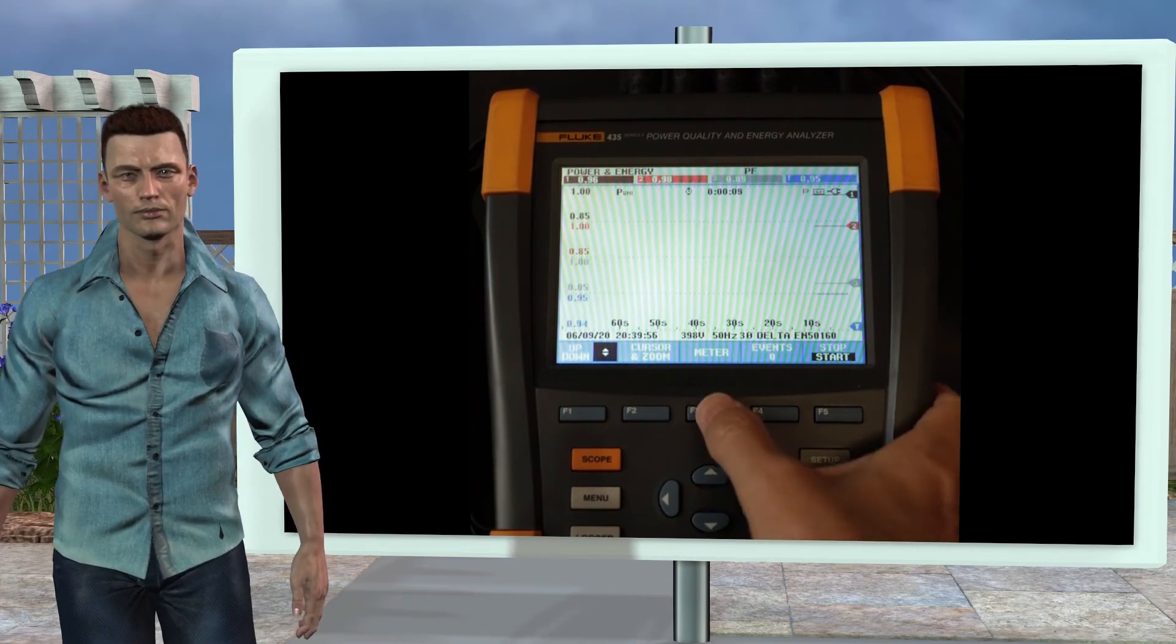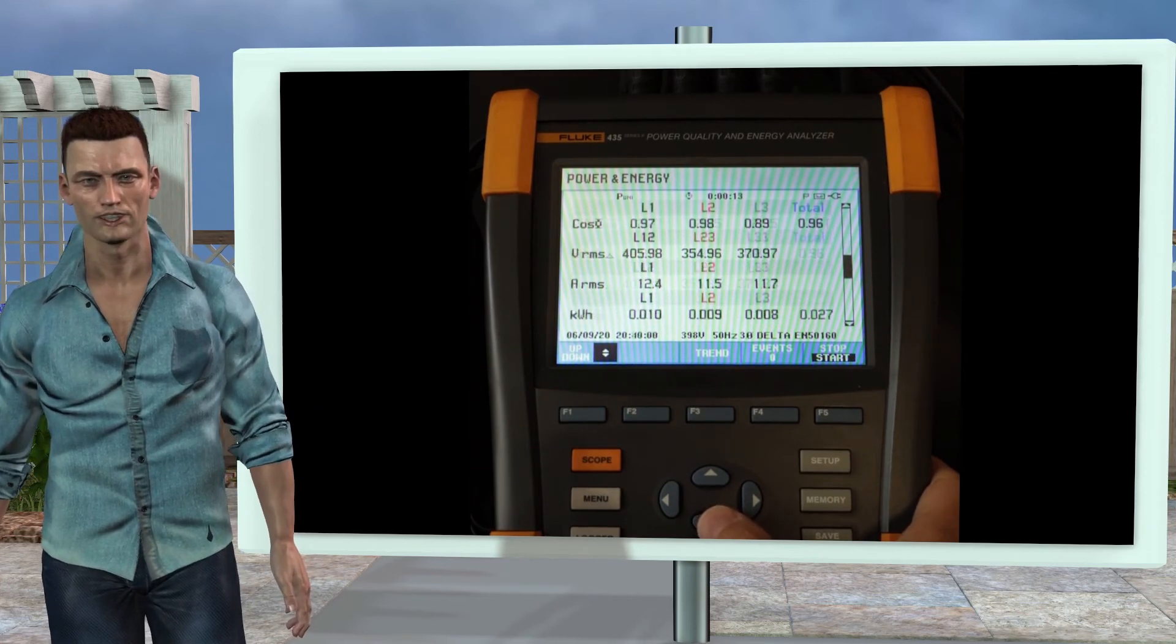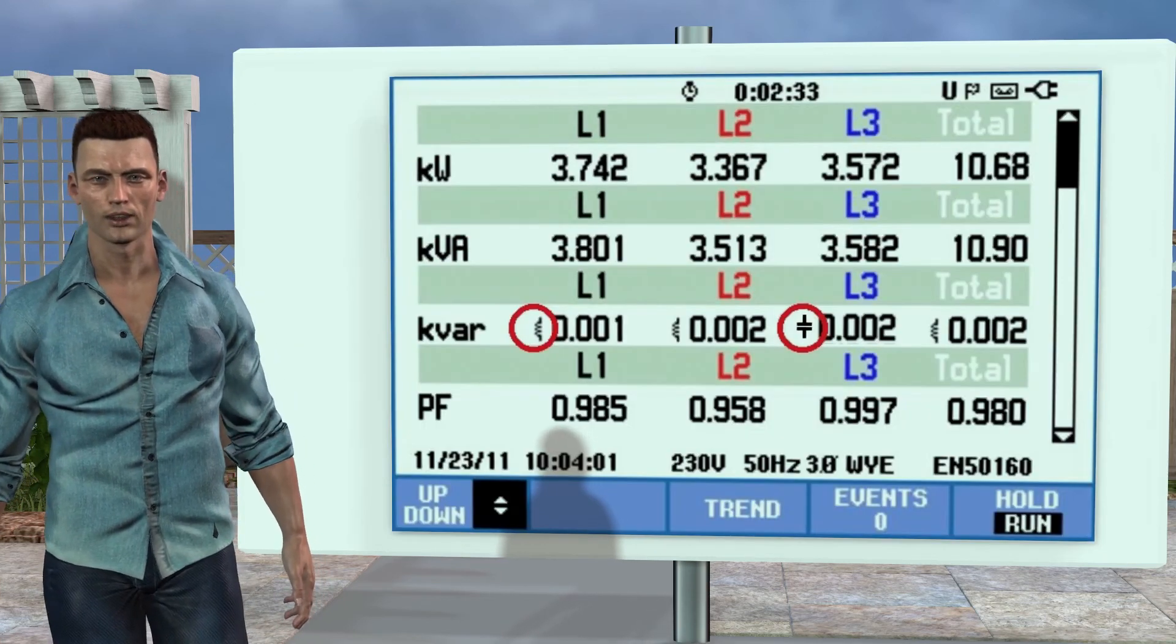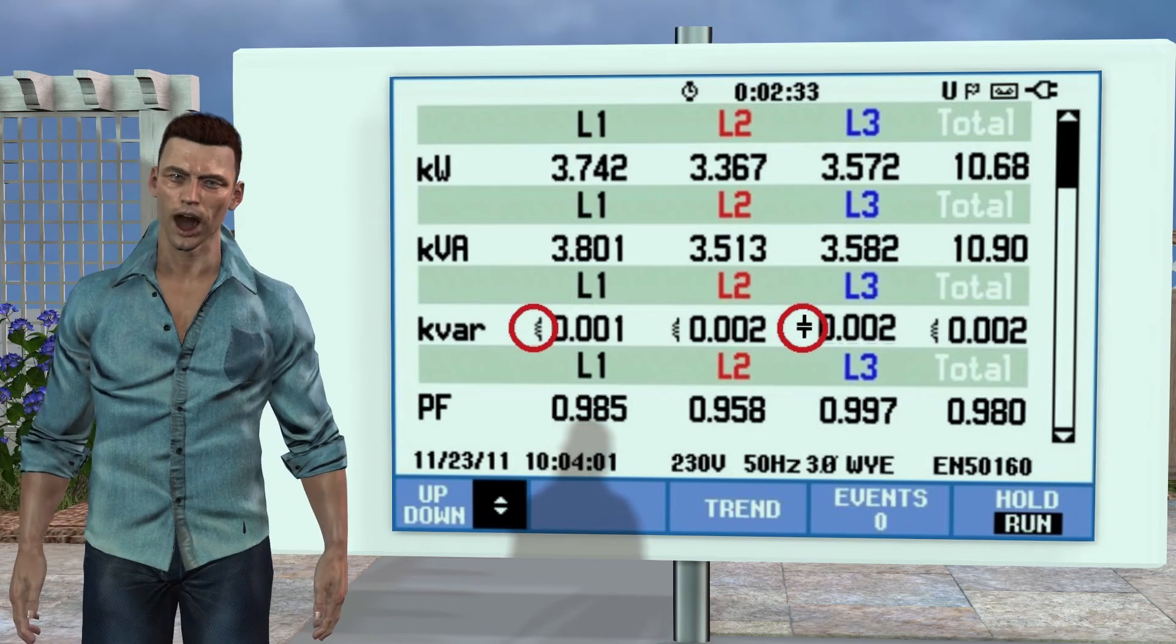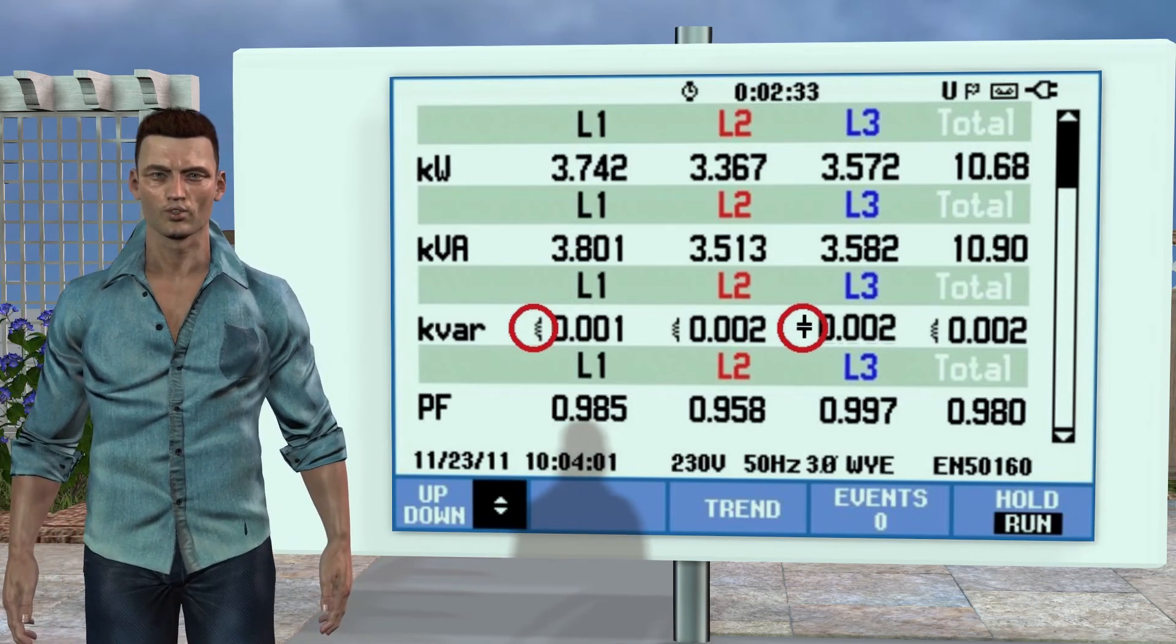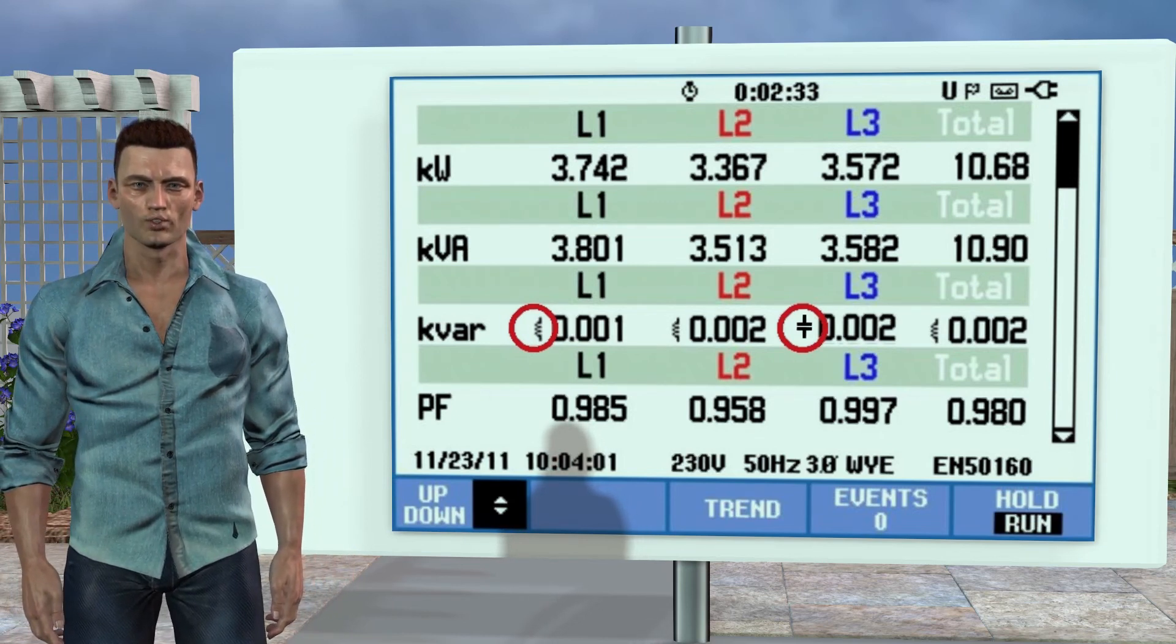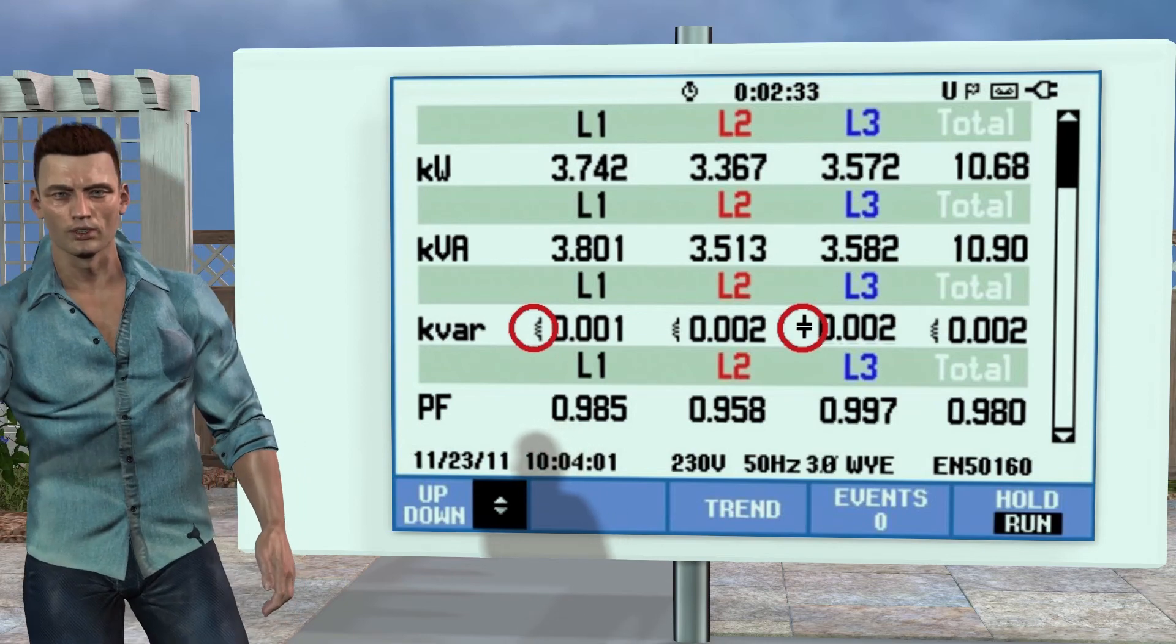As I have already indicated, reactive power appears on inductive circuits, but also on capacitive circuits, and, in order to be aware of what type of reactive power we have, the Fluke 435 provides, for each phase, an icon or symbol, of a capacitor, or a coil, if the installation is capacitive or inductive, respectively.